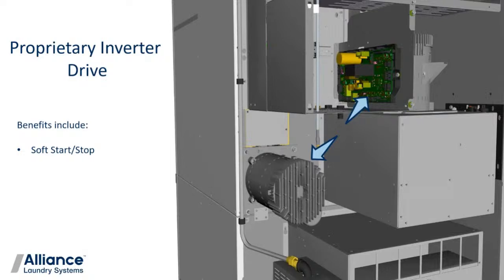So the first benefit to using an inverter driven motor on a tumbler is it has a soft start. You press start, a little delay in processing, and then slowly it comes up to speed. That provides us with a really, really low dB operation, meaning it's super quiet. Tying into the soft start stop, that also gives us a longer belt life. We're not asking the machine to turn right away, so we're not jerking the belt. We're actually just ramping it up real slow. So from an operational standpoint, we get the idea what's going on: quieter, easier on the components like your pulleys and stuff like that, your motor.